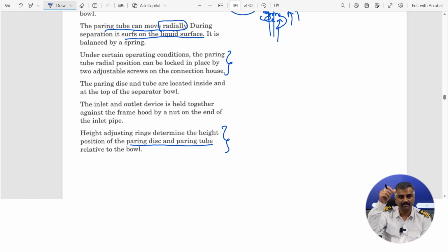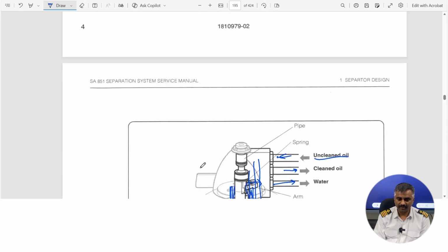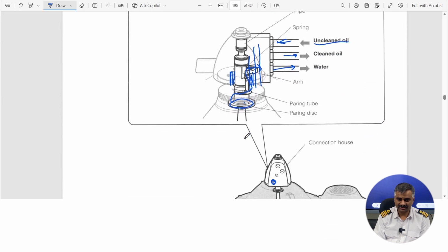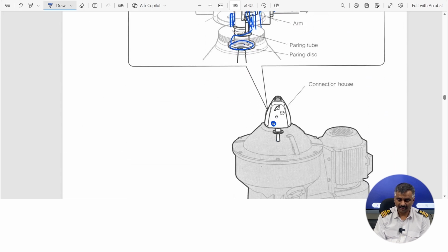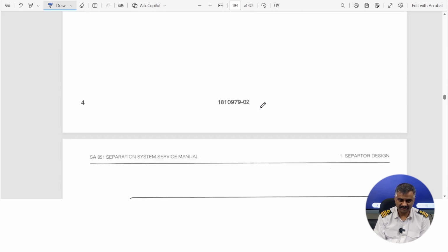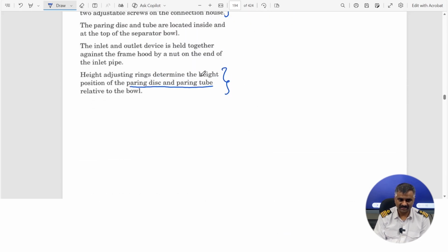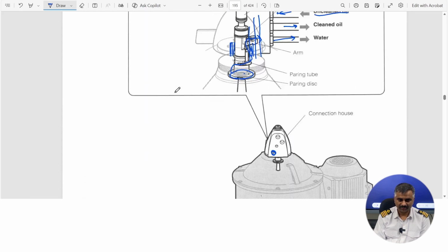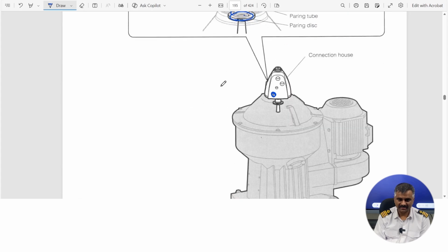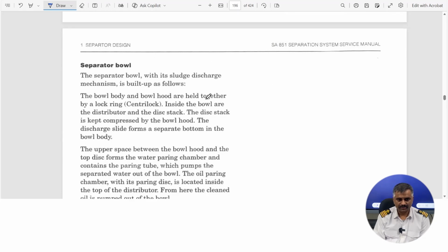This is important in the Mitsubishi Purifier too—after complete assembly, we measure the distance of the spindle from the lock nut. Similarly here, relative to the bowl, we always measure the distance of the part from the top. The height of the adjusting rings determines the position of the paring disc and the paring tube relative to the bowl, so that height is also important.